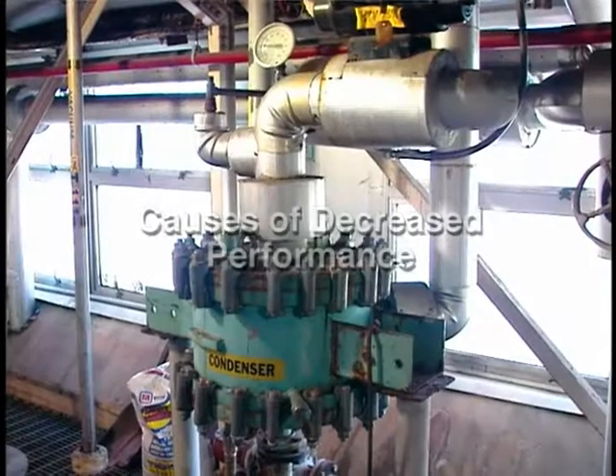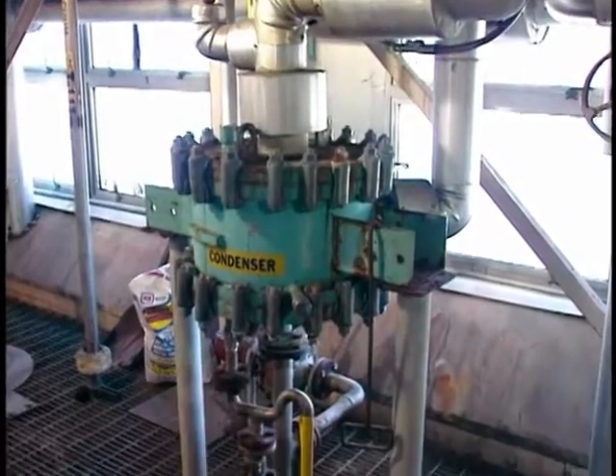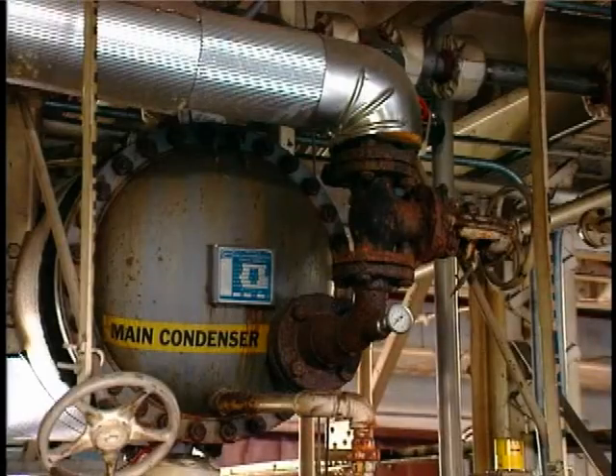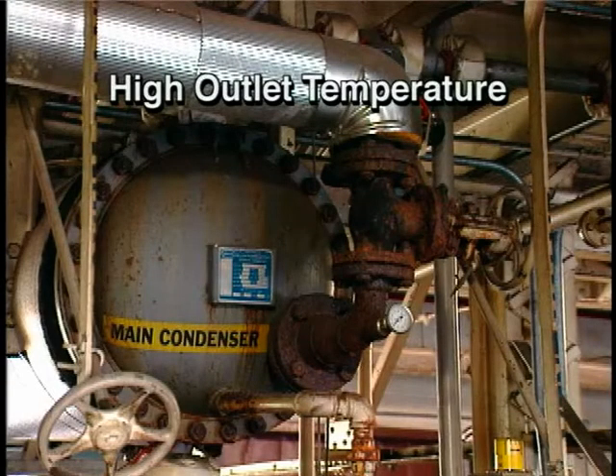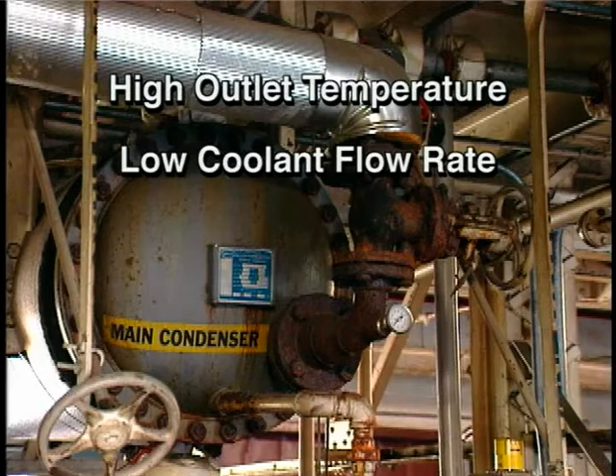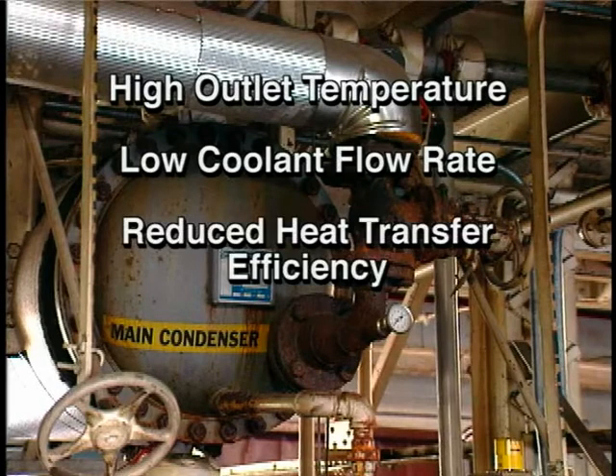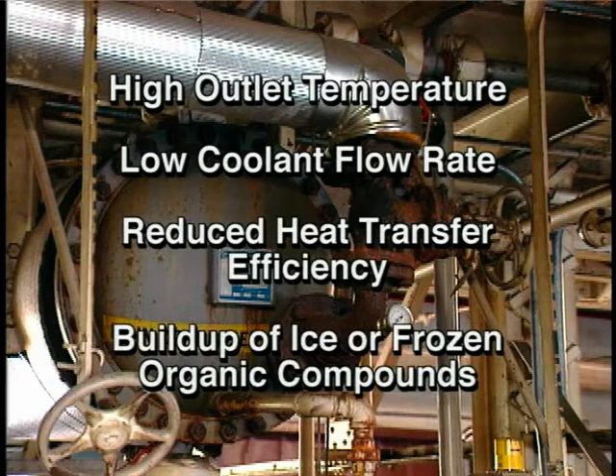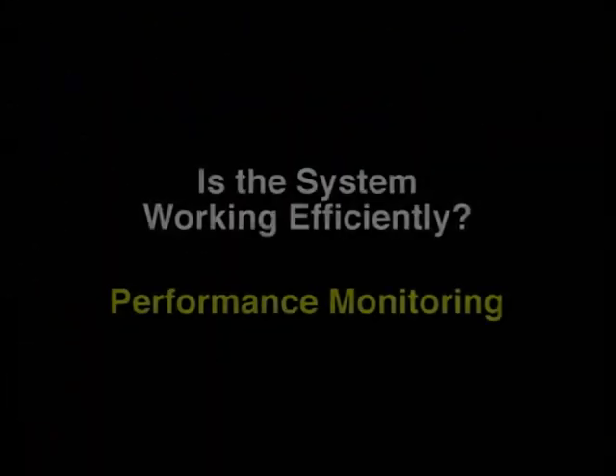There are several factors that contribute to loss of performance in condensers. These problems include high outlet temperature, low coolant flow rate, reduced heat transfer efficiency, buildup of ice or frozen organic compounds.